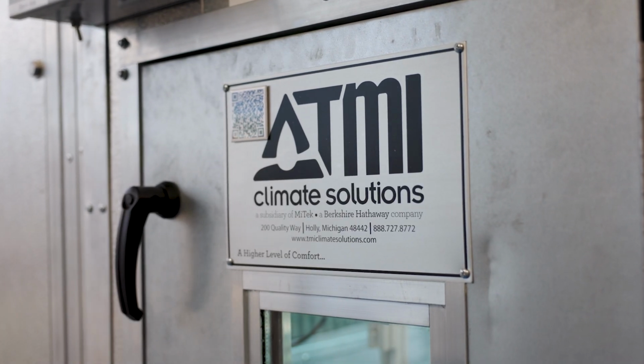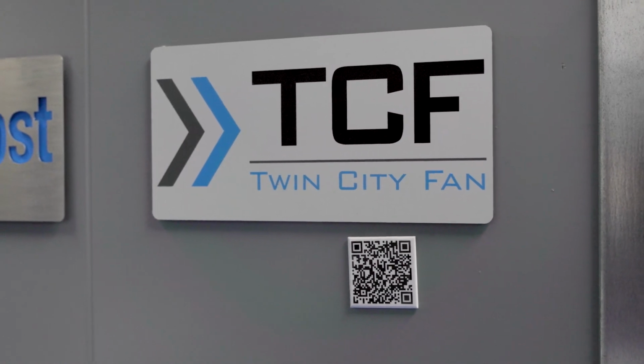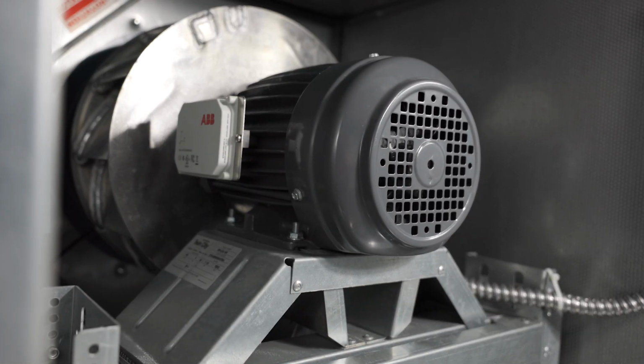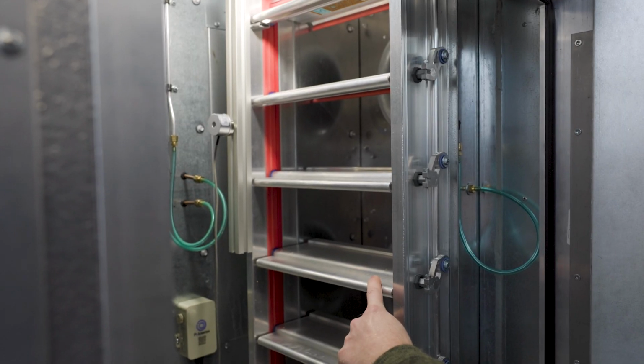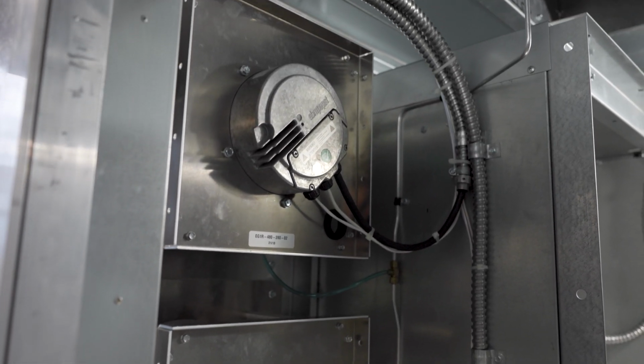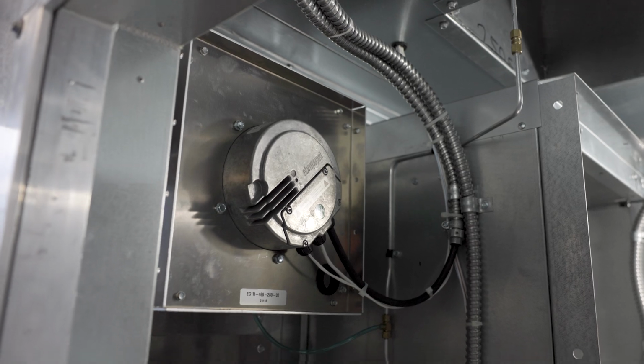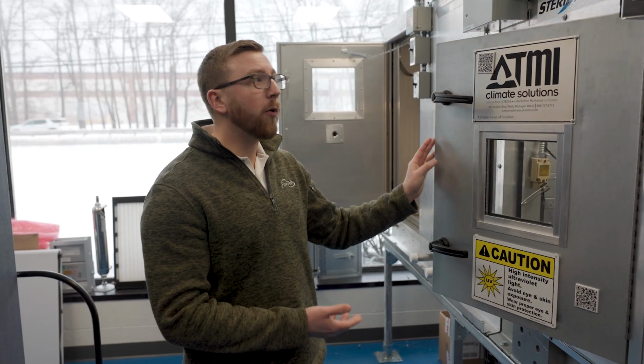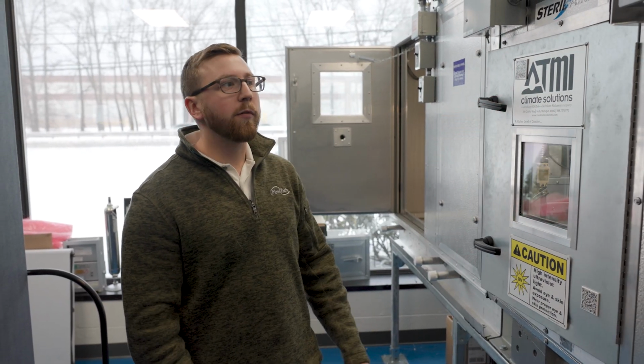Another fun application about our unit is we have 3 different fans in this unit, and you wouldn't typically see this in this application. On the far side, we have a Twin City fan AC fan, which is controlled by a VFD on the wall. You also have some backdraft dampers. On the closest side to me, we have 2 EBM PAPST EC controlled fans. So you'd either see EC or AC, you'd never see them in both, but we wanted to show off the capabilities that we have here at Flowtech.